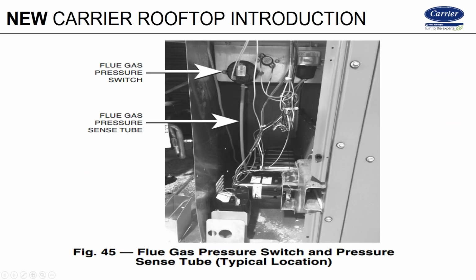So, where are we at here? Okay, so we used to have Hall effect sensors, Hall effect switches, to prove induced draft motor operation. We've since, and not just on this Vane-Axial fan unit, but prior to that, on the TCs, HCs, KCs, we went back to a pressure switch. We did this as a request from the field overall throughout the nation, because there were a lot of people that just didn't like that Hall switch and how you had to troubleshoot it.